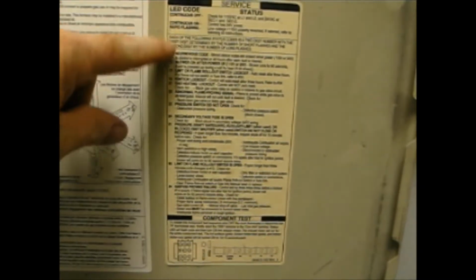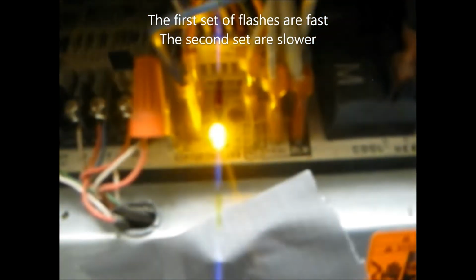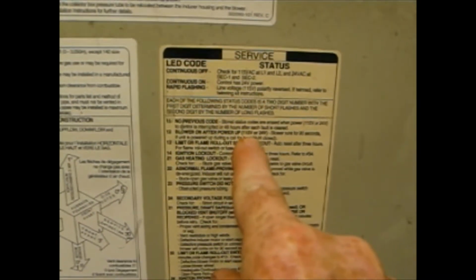Just about every circuit board will have an LED light that will flash a code. Generally, on the back of each furnace door will have an LED code, depending on the types of flashes. When we go to turn this on, this LED light will start flashing 1, 2, 1, 2. When you come back to here, you can see that it says blower on after power up, which is a common code when you interrupt the normal procedure of a furnace.